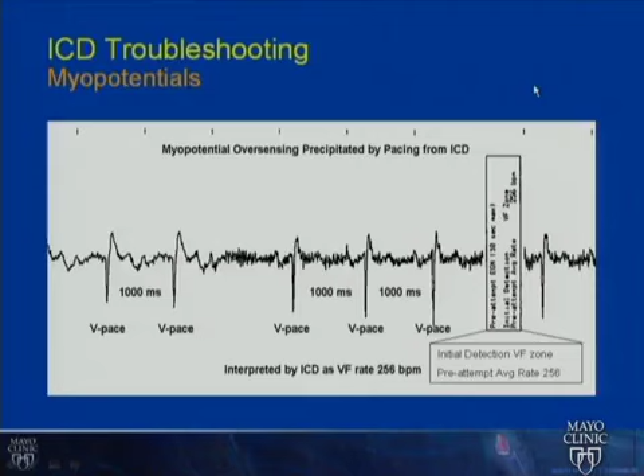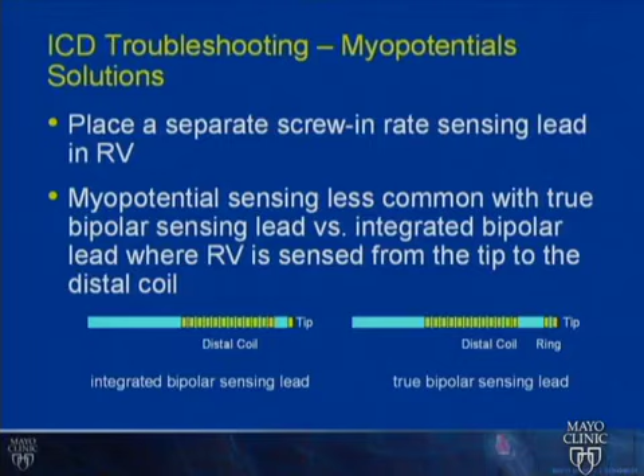When this type of oversensing occurs, one could consider reprogramming the device to a less sensitive setting, so that there will be a reduced chance of the device sensing these low amplitude and rapid signals. But on the other hand, anytime an ICD is reprogrammed to a less sensitive setting to avoid oversensing, one must make sure that reducing the sensitivity of detection does not compromise the detection of ventricular fibrillation. That's the time you would want to take the patient to the lab to do a ventricular fibrillation induction and check the defibrillation threshold, to make sure the device continues to adequately detect ventricular fibrillation when you change the sensitivity.